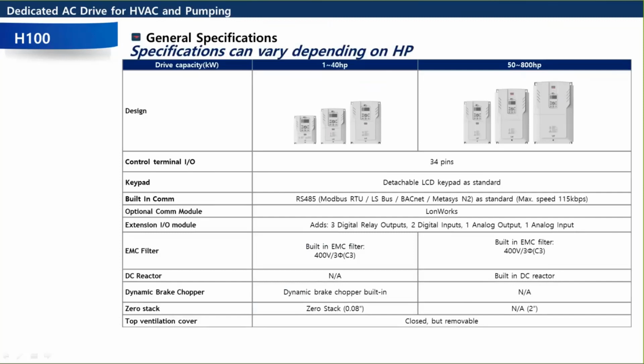We have the built-in EMC filter on the 480 volt ones. And there's a few sizes that don't have the EMC filters. I think there's a slide that comes up about that. So it depends if you need it or not. And then the built-in dynamic brake chopper is up to 30 horsepower standard. Well, 40 horsepower since this is normal duty.